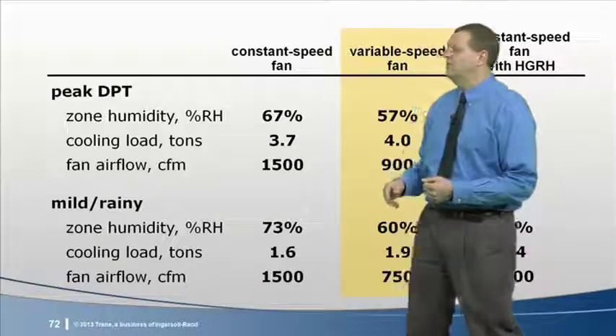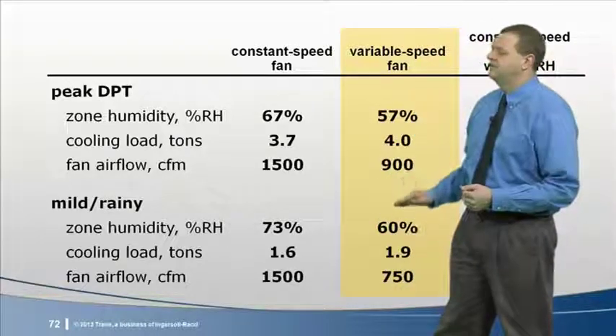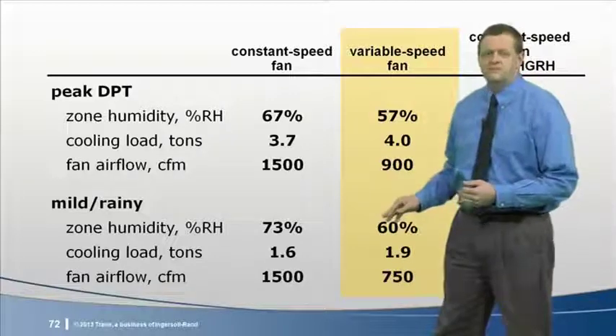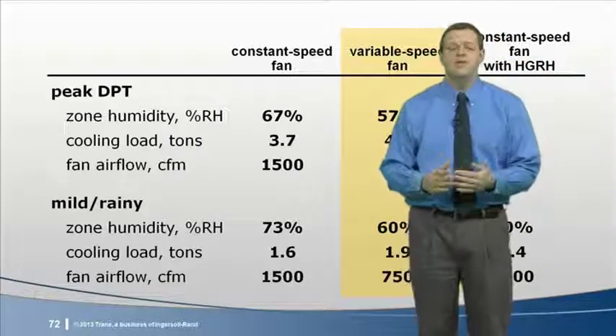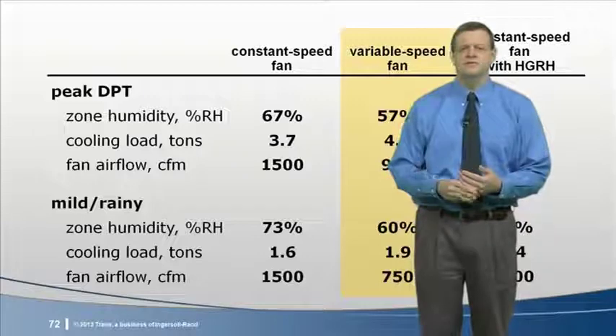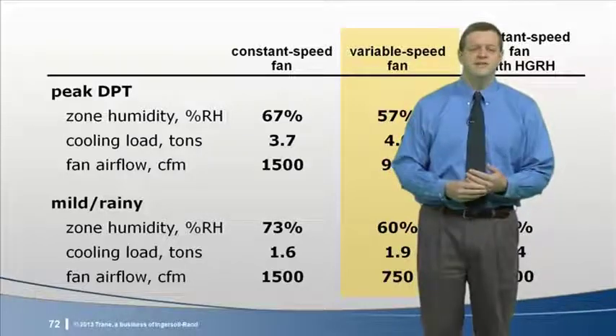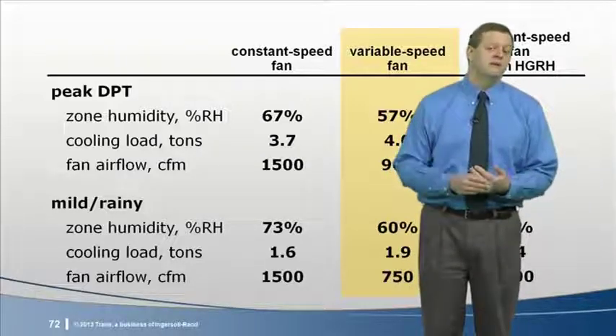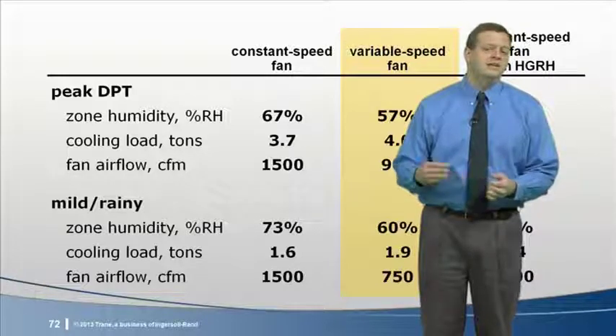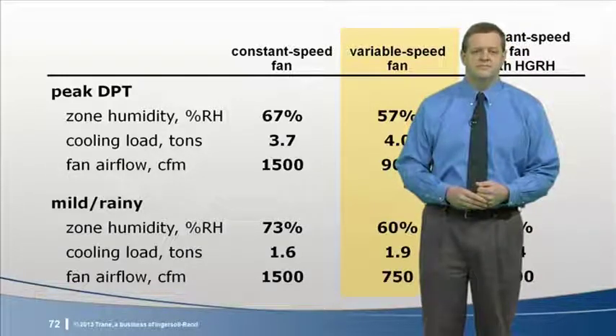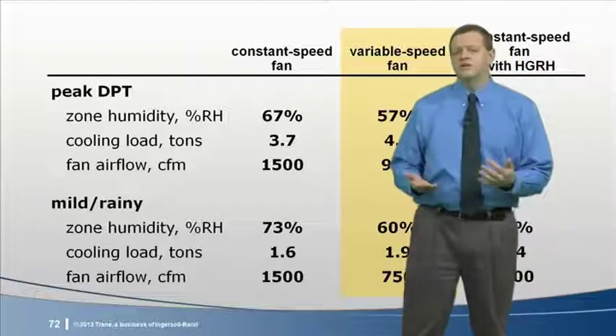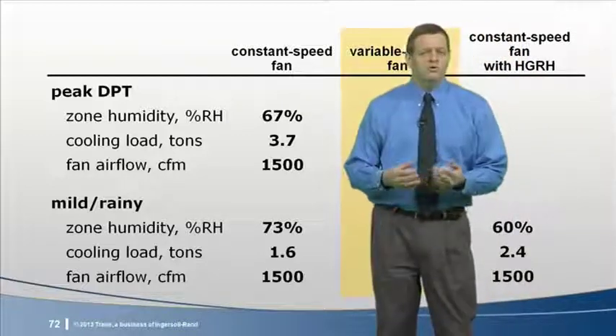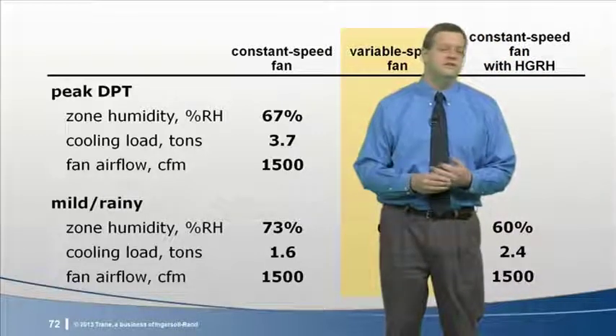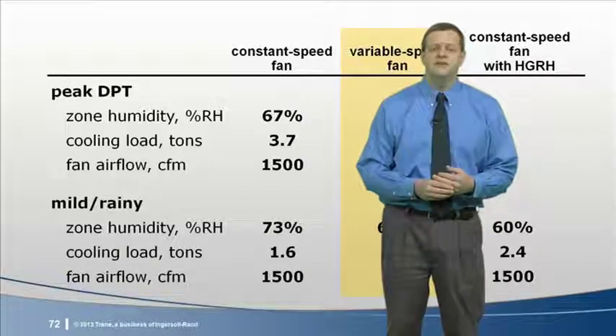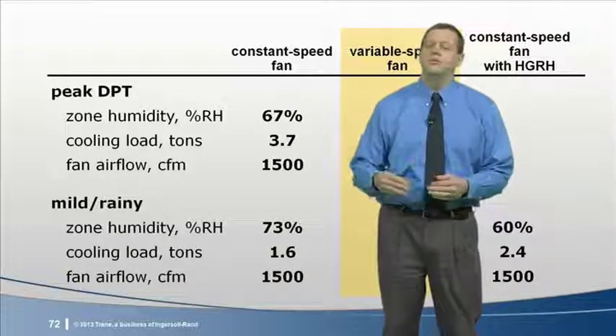But if a project requires lower space humidity levels than the SingleZone VAV system can achieve, some types of equipment can be equipped with hot gas reheat also. In that case, the variable speed fan will likely limit humidity most of the time, but the reheat can kick in if it's ever needed. In the case of fan coils or water source heat pumps, a more efficient approach would typically be to use a dedicated outdoor air system to dehumidify the outdoor air centrally, rather than equip each local unit with reheat.